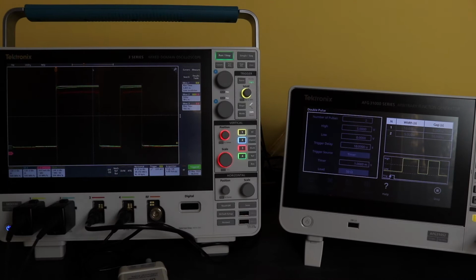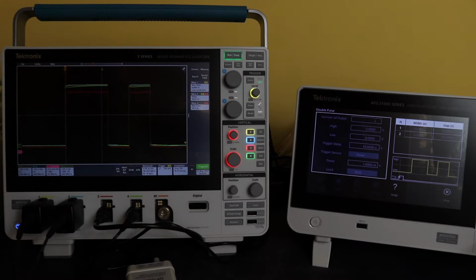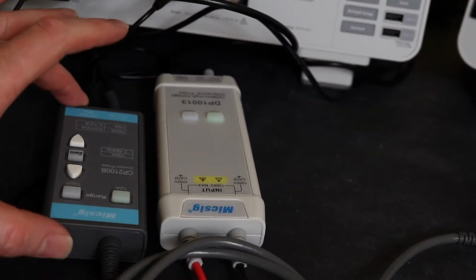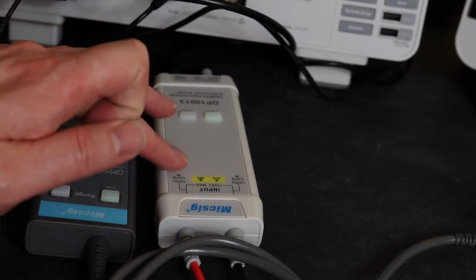So once the double pulse software has been loaded, what I need to do is check the timing difference between all 4 of my channels on the oscilloscope. The primary reason that's being done is because I'm using a current clamp to capture some of the signals. Okay, so this is the current clamp, and this is the differential voltage probe.